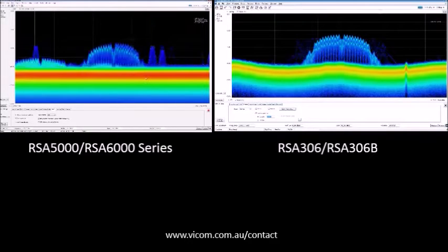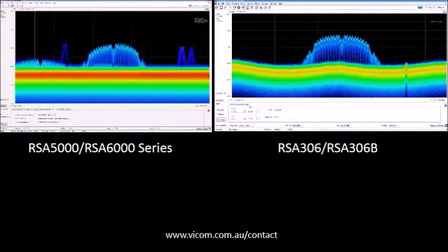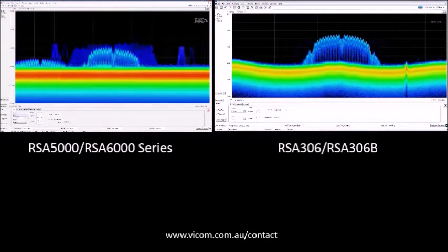The last thing you can do here, which is also really unique, is all the trigger functionalities. If you've been to the trigger menu, the trigger bandwidth is always 40 megahertz and you can just level trigger. If you go to the trigger on this one, you have RF input, you have power, but you also have frequency mask, density and runt. And there is also time qualification. So there's a little bit more trigger capability.